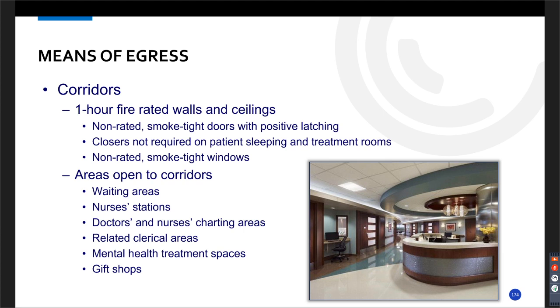The closers aren't required on patient sleeping and treatment rooms as long as those doors do not open into the required width of the corridor. They open into the room, they don't need the closers. Or if they open into a corridor and the corridor is more than the required width, then they may be able to. But anyhow, can't open into the required width corridor. And then non-rated smoke tight windows. Those have to be all in the corridors.